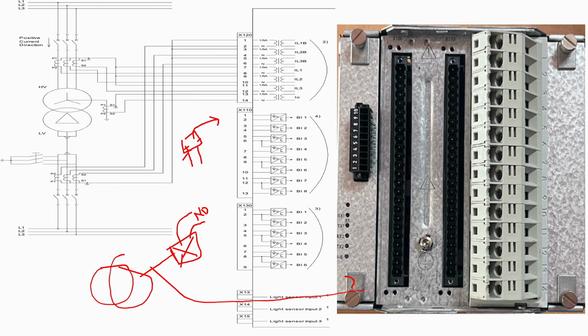The same fundamental. You can utilize your binary inputs for any interlocking purpose, for indication purpose, for alarming, for LED, any kind of use. Okay, whatever your requirements, it depends on your requirements. So here, what we will do, we will give negative directly to the binary inputs. So we require a positive here. So we connect positive here on one side, and the other one, the potential free wire, will connect to the binary input positive terminal.